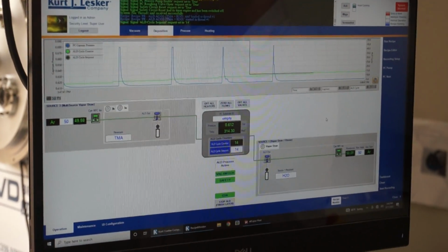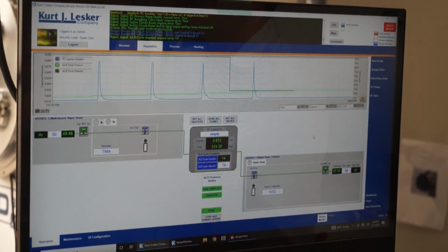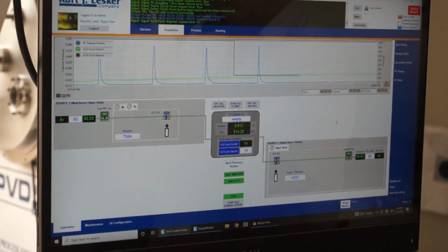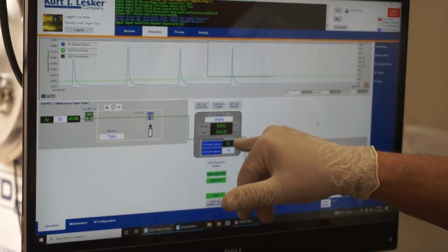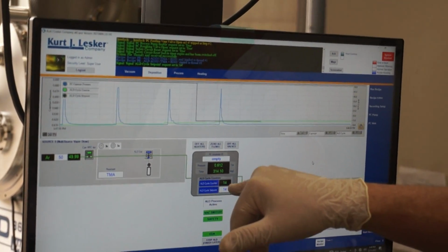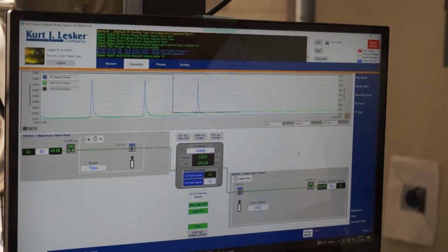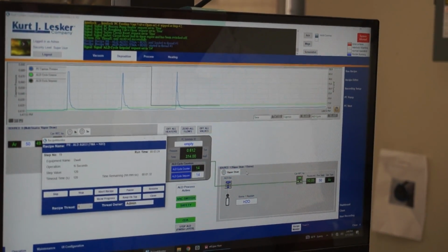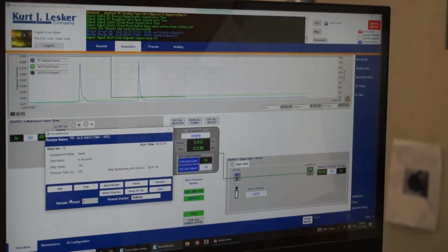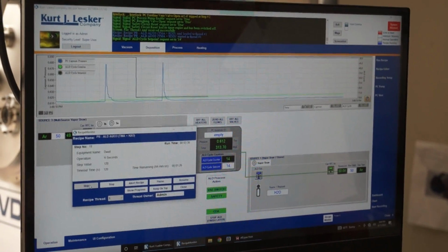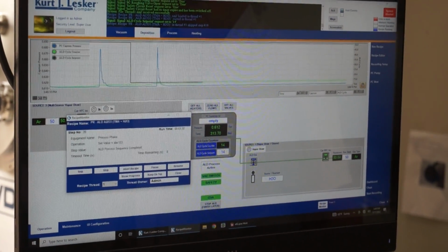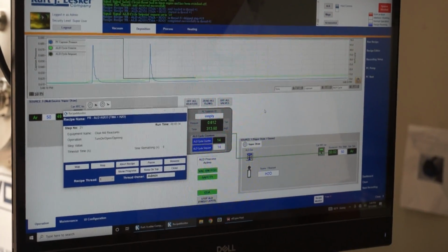Might put it in a state, then the next time you run the process, you might have a hiccup you gotta overcome because you skipped a normal step. So I wanted to shorten it. Instead of 50, I just brought it up to 14. That'll allow the recipe to finish how it normally does. I'll skip this 120 seconds, 2 minutes, because I already know this is conditioned.